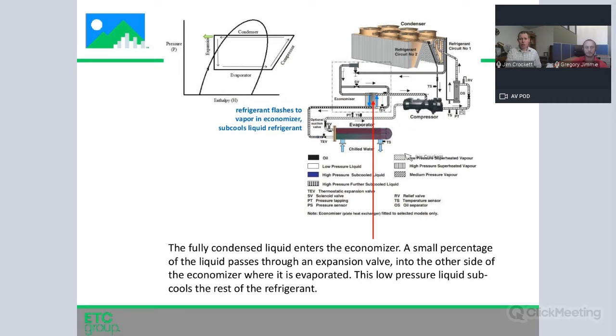In this particular case, we have an economizer as part of the system. So we have liquid coming off of the condenser. We take a small part of that and flash it. In other words, we cause it to evaporate, which makes it absorb heat from the surrounding areas, or from the economizer in which it is. We take the balance of the refrigerant and run it through that economizer. So we pre-flash, we sacrifice some of our refrigerant to cool the rest of it down.